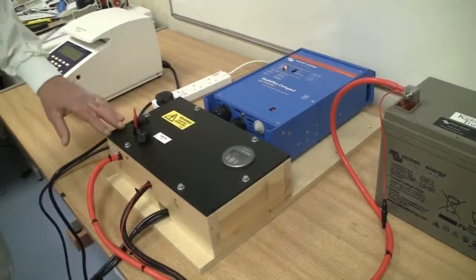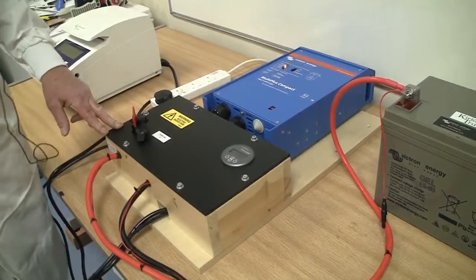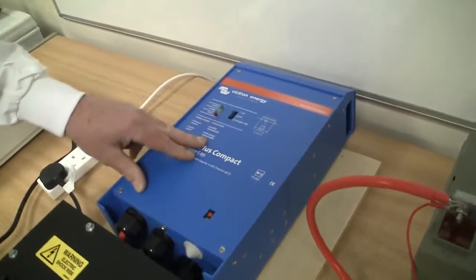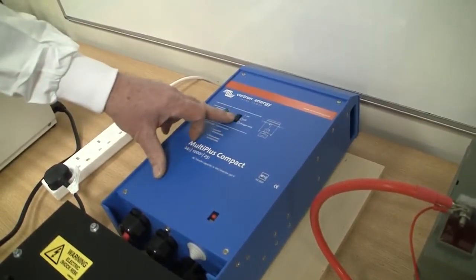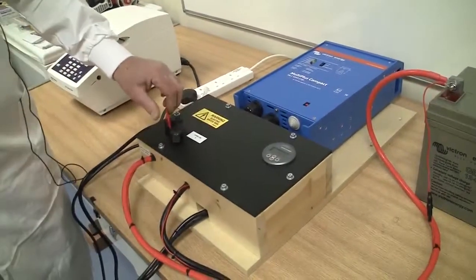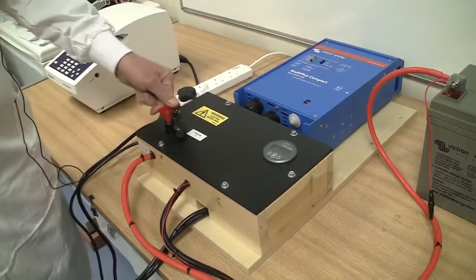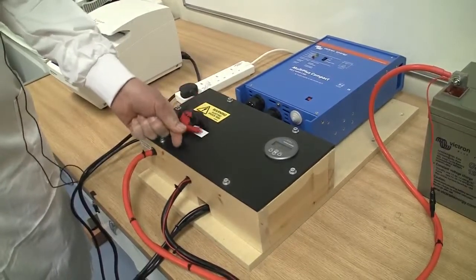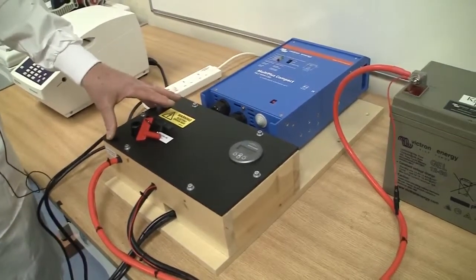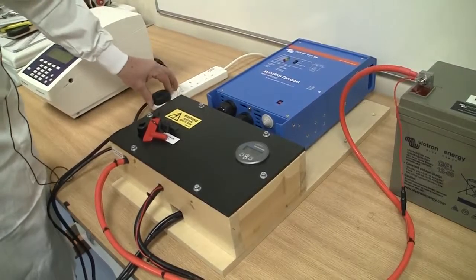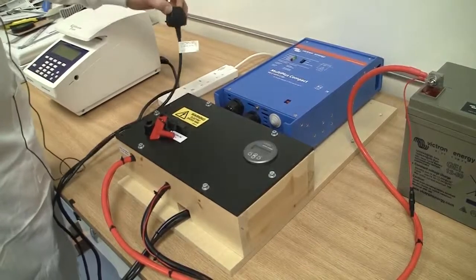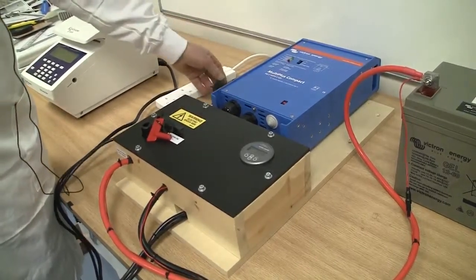If you were going to turn off the equipment the way in which you would do it would be to turn the inverter to the middle position which is off from on to off. You would likewise before you touched the batteries make sure that you turn the key to the upright position and take it out. Then you know for certainty that the electricity from the mains will no longer reach the batteries. If you are indeed using a plug rather than it being wired in you can remove the plug and then you are totally isolated from the mains.